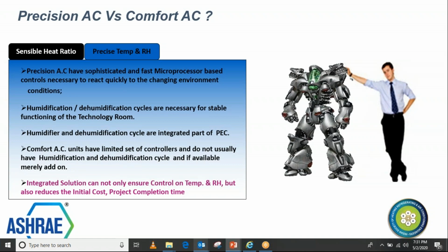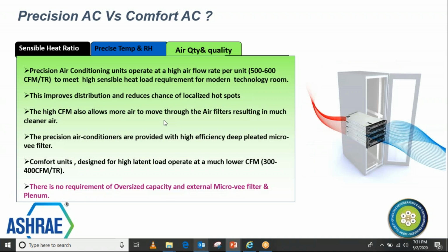On the temperature side, obviously, high temperature will lead to component failures. There can also be issues when it goes to a lower temperature, leading to fatigue-type problems in the component. So we must ensure that precise temperature and humidity are maintained in critical environments. And these points differentiate precision AC from comfort AC.